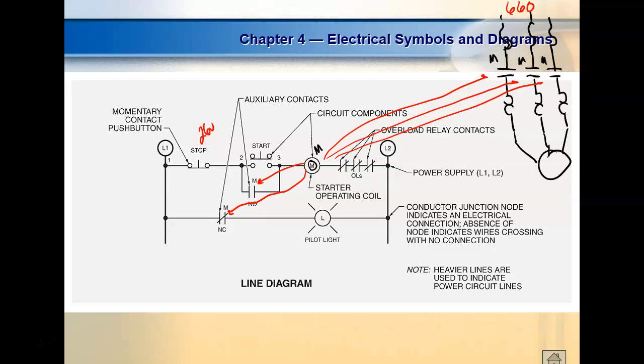And that's what's so nice. What you control with that light switch, it's just a switch rated at 15 amps up to 150 or 250 volts. So what can you run with that? Could you run DC through that thing? Sure, yeah. It's just that you don't want to exceed 250 volts at 15 amps. If you do, then it's not guaranteed to open the circuit anymore.